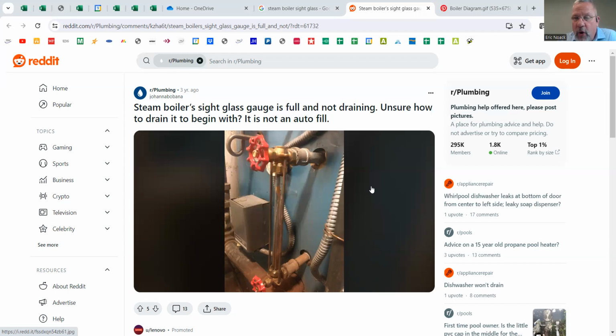Okay. So the homeowner might know if it's steam or not. But the sight glass is going to be one of the key things, and then also that blow down valve and no circulating pump. The other key one is much larger piping. Usually steam boilers are going to have really huge supply piping. Sometimes, oftentimes in older homes and older buildings, it was originally steam and then it was converted to hot water. So it could have the same large piping and the same radiators, but they've been converted for hot water.